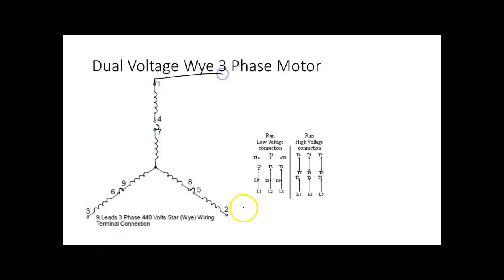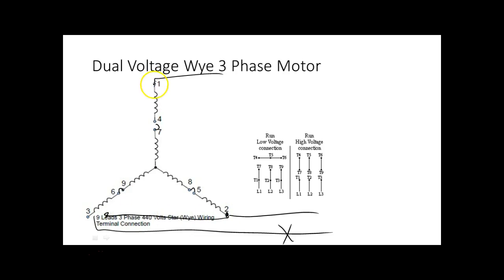So what happens is I come over here and I've lost this phase right there. As soon as I connect here to here, I still have a connection between this phase and that phase. My meter's only 10 mega ohms, so those coils aren't going to drop hard. It'll be a little lower, but there's still going to be a voltage there, probably over 200 volts. But you can't get any work out of it because there's no current available from that phase.